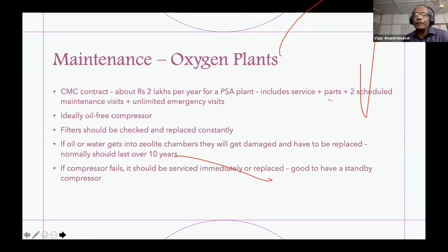An important thing is maintenance. If you give the maintenance to a company, it costs about 2 lakhs per year for service and visits. Ideally there should be an oil-free compressor, and filters should be checked and replaced constantly, otherwise it will damage the zeolite chambers. Normally the chambers should last more than 10 years, but if oil, air, or water gets inside, they get damaged.